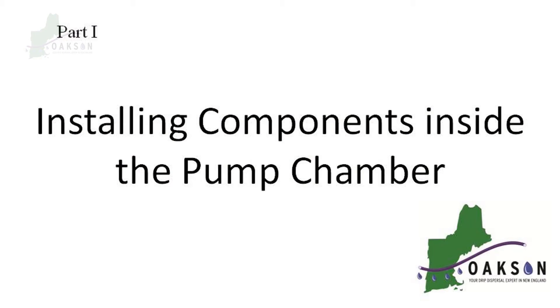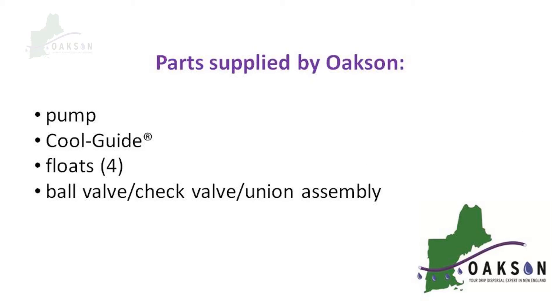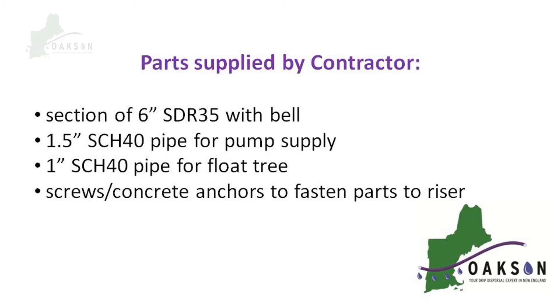In part 1, our focus will be on all of the components inside the pump chamber. Oakson will be supplying the pump, the cool guide mounting mechanism, all your floats, and the valves that connect your pump to the supply line. The contractor will be supplying a length of 6 inch SDR 35 with a bell, some inch and a half schedule 40 pipe for your pump supply, one inch schedule 40 for the float mast, and some fasteners to tie everything together.